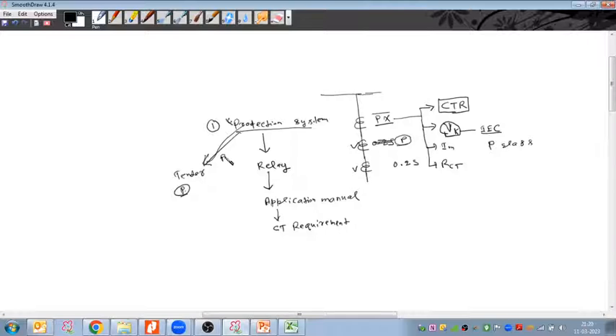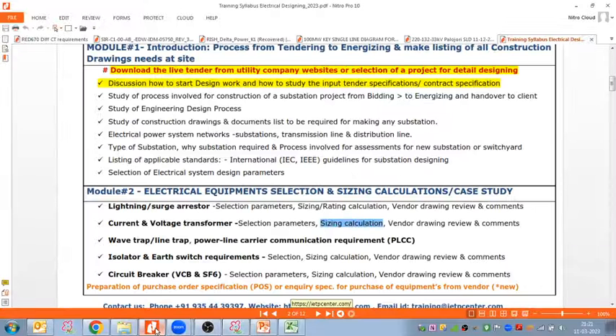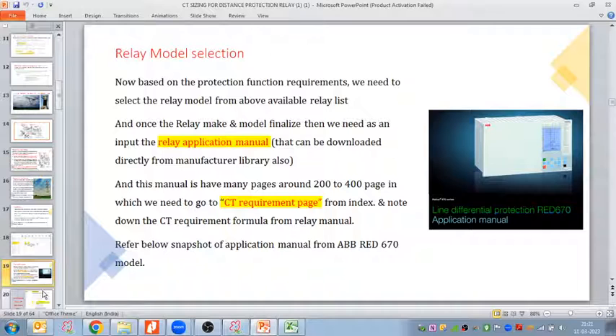Yesterday we referred to the PGCIL control and protection technical specifications given by Power Grid to all their contractors, and from that we understood what kind of protection system is required by Power Grid. Based on that we selected the relay, the application manual, and the CT requirement formula. We need to check there. Now, going back, these things we have already discussed.